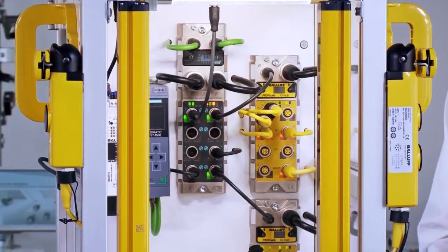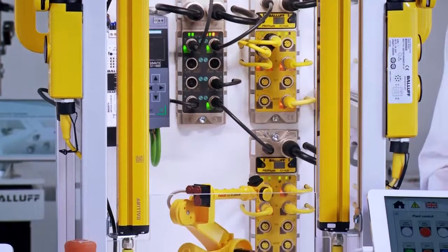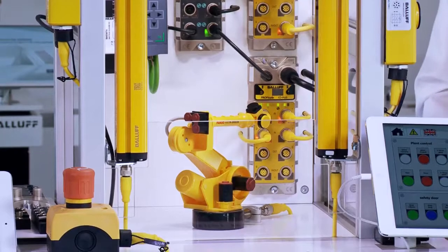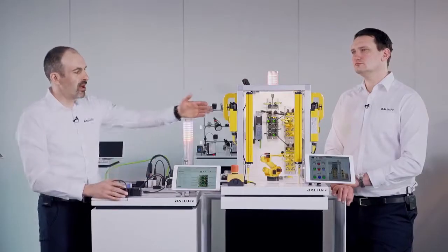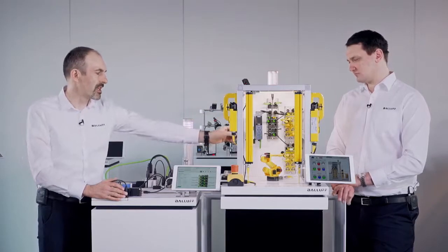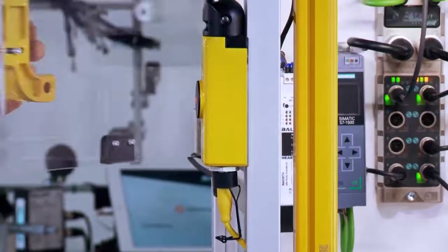What is important? Universal in that case means that you use a standard safety PLC. Standard in that case means the PLC has to be equipped with the safety function, but as universal you connect traditional safety devices. So if you use any kind of standard light curtains, safety button, or safety switch to protect some housing, or magnetic field sensors, and different kinds of safety devices, all of them can be connected to such a module, which collects the safety signal and sends it directly to the safety PLC.